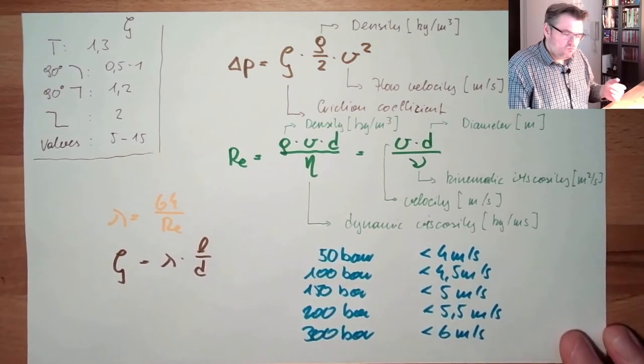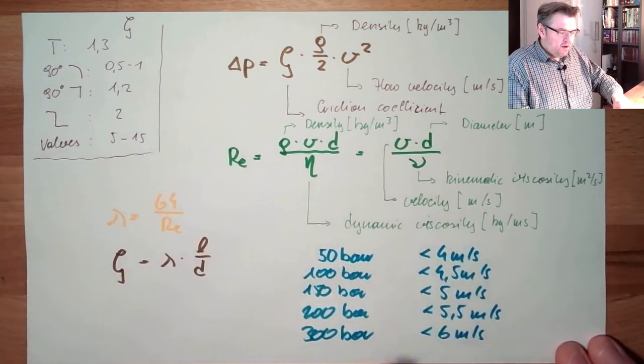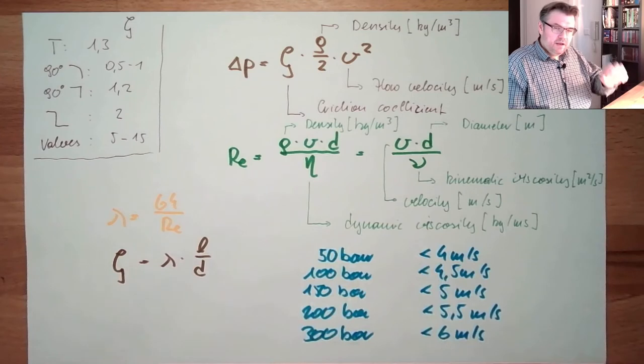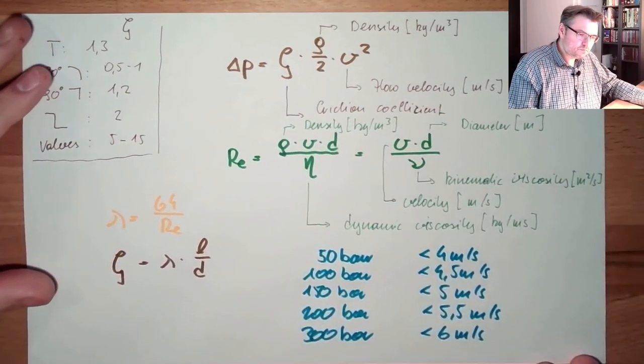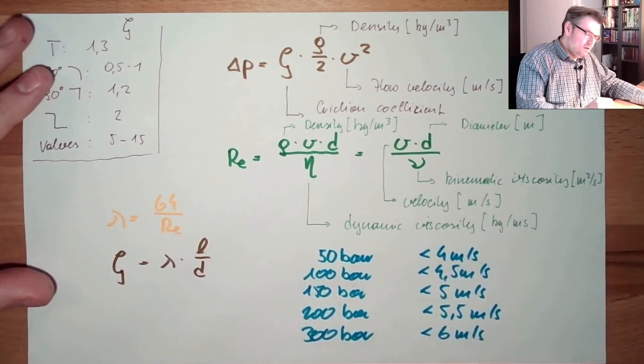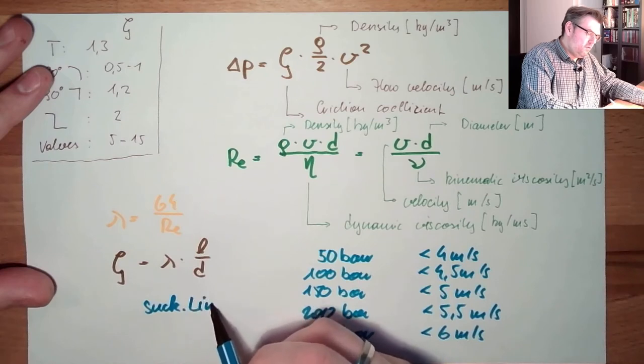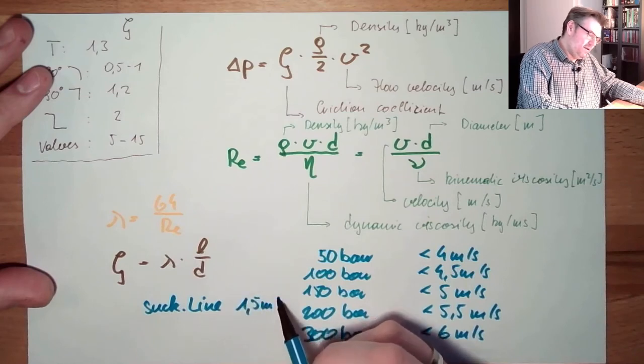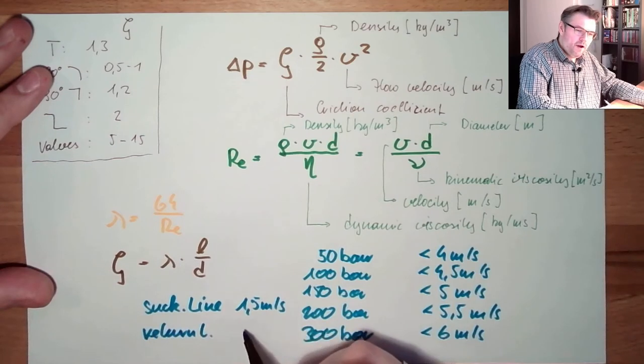These are rule-of-thumb methods. With this average flow velocity, I can already design the diameter of my tube and then calculate the Reynolds number. For the suction line, the flow velocity is about 1.5 meters per second, and for the return line we have 2 meters per second, because here there shall be no pressure — in fact it can be below atmospheric pressure.